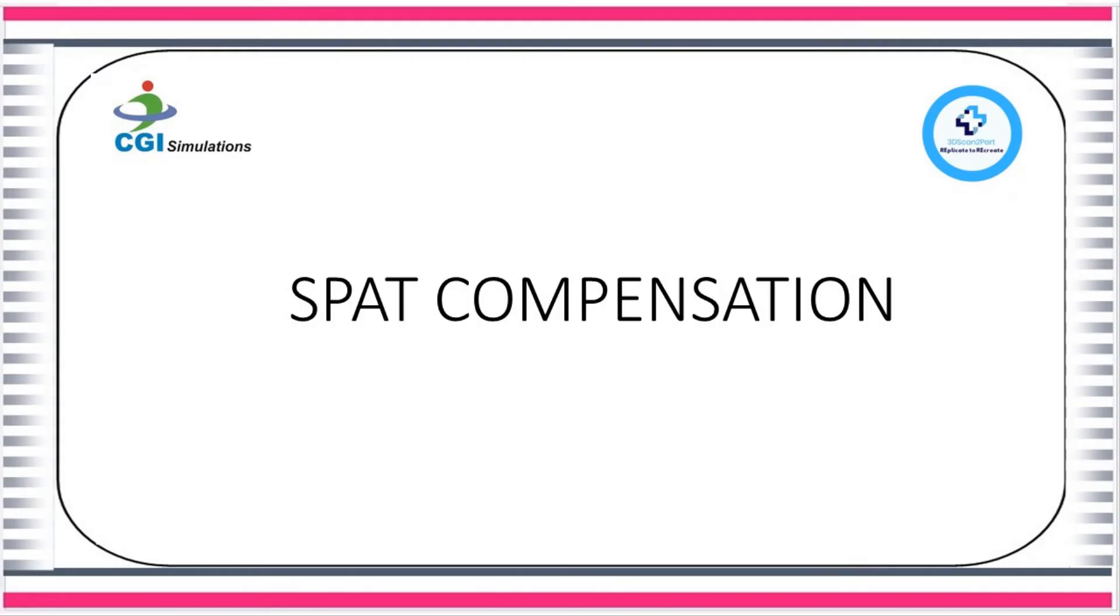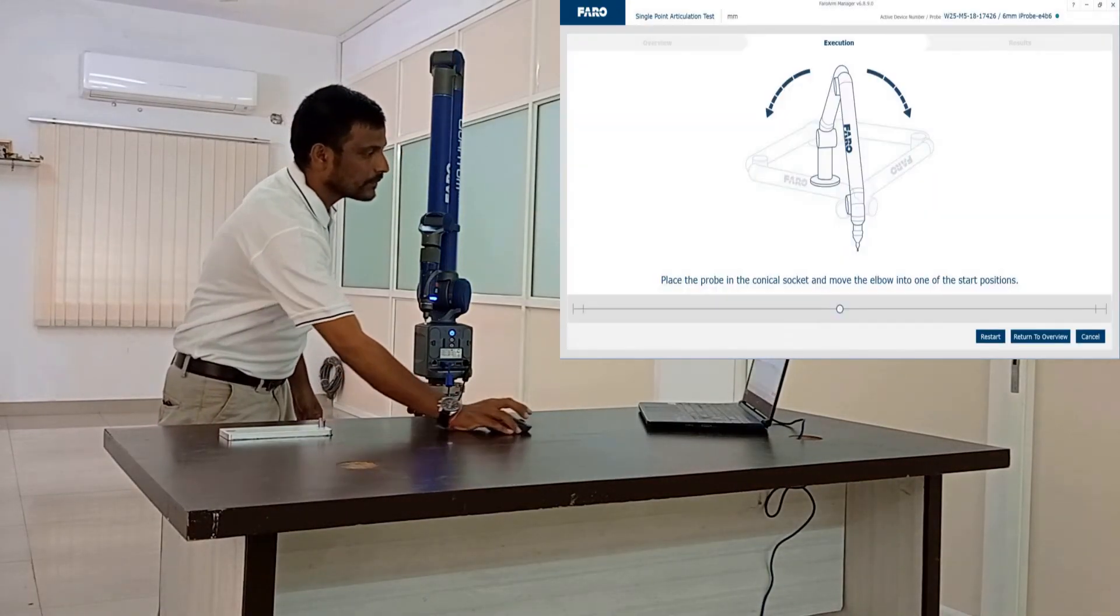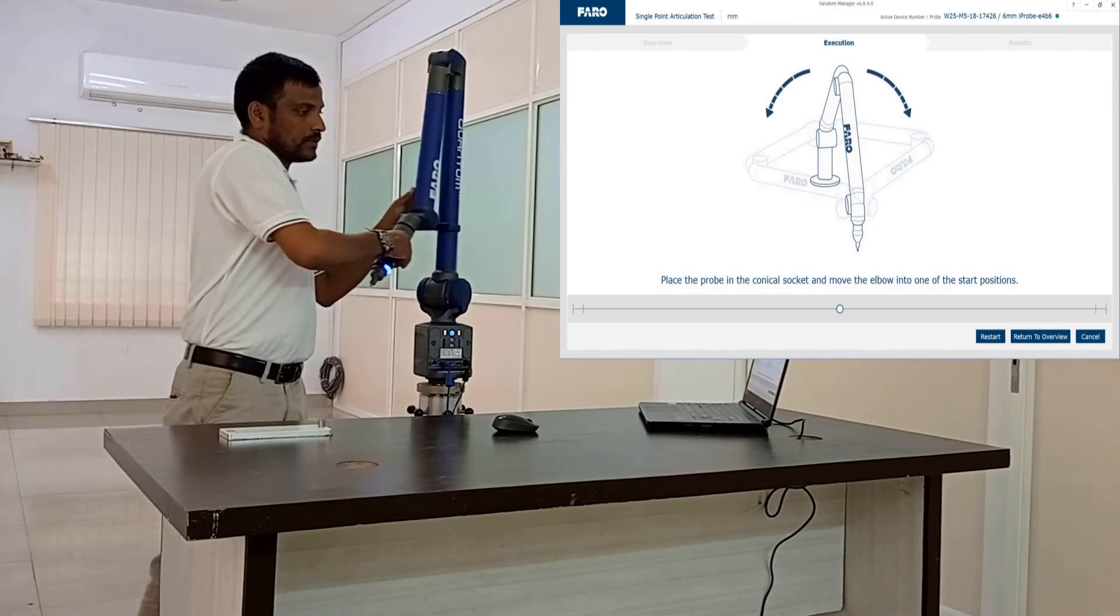Let us do SPAT compensation. SPAT stands for single point articulation test. In the Faro arm manager click on SPAT compensation. Place the probe in the conical socket.